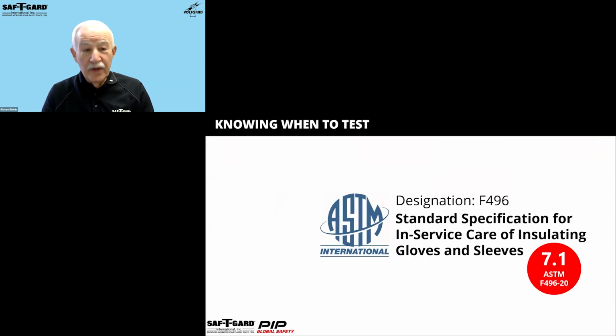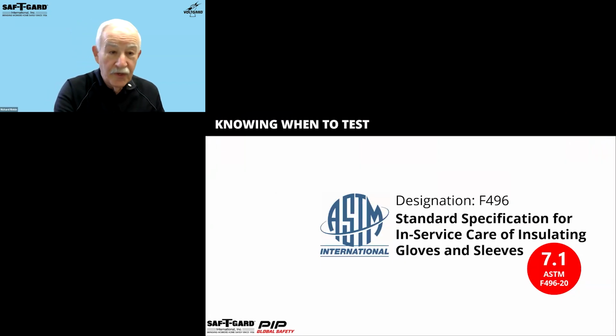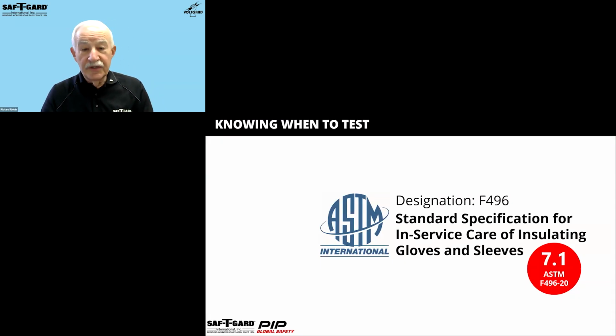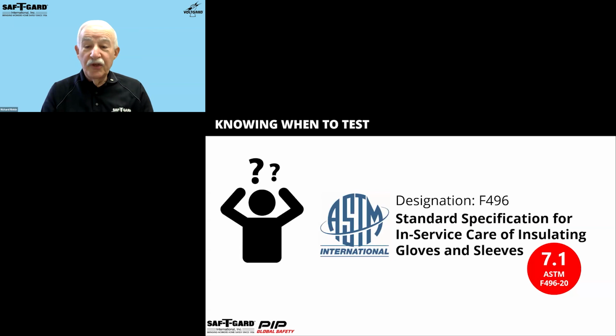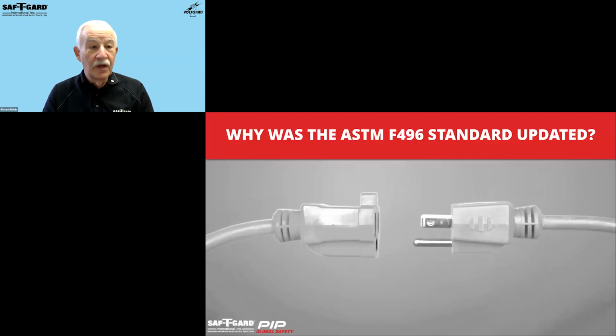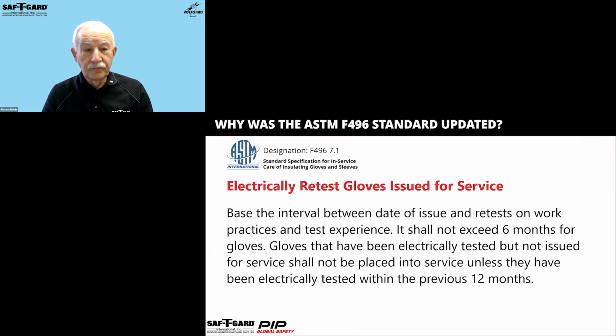As I explained, they're always inspected and tested at the manufacturing facility, but once they're in service, there are periodic retest intervals that are specified in ASTM F496, the standard specification for in-service care. Previously, this standard was subject to interpretation and misunderstanding regarding the maximum test interval for either new rubber insulating gloves or in-service rubber insulating gloves. So the ASTM committee got together and in 2020 updated and simplified the language.